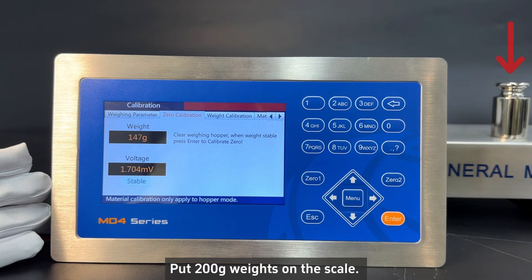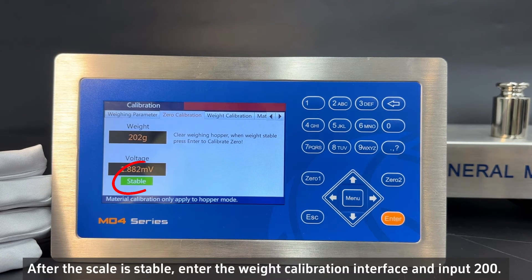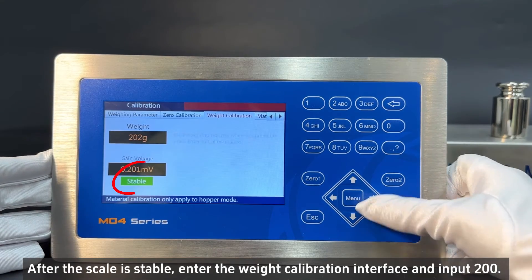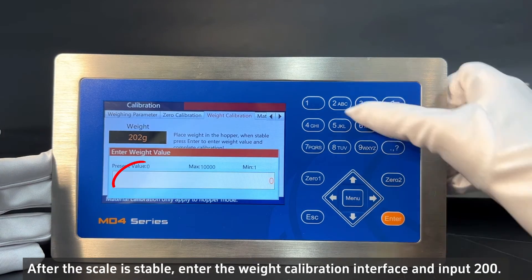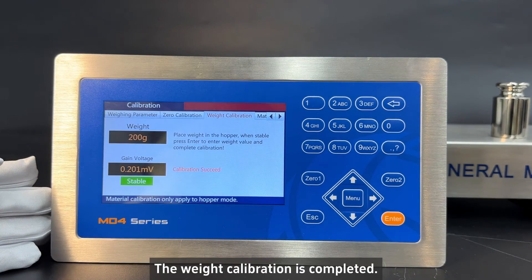Put 200 gram weights on the scale. After the scale is stable, enter the weight calibration interface and input 200. The weight calibration is completed.